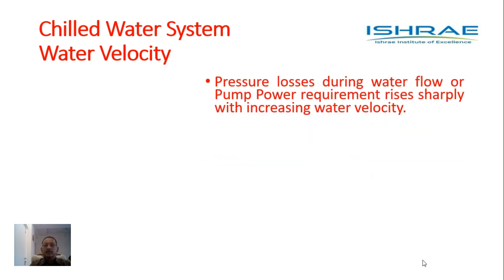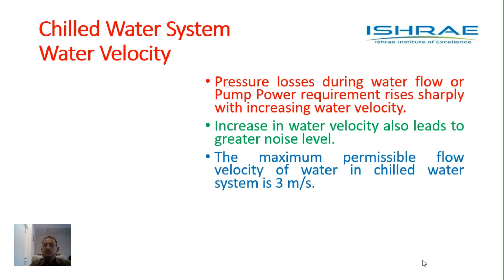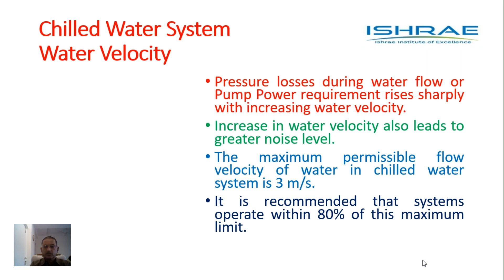Pressure losses during water flow, or pump power requirement, rises sharply with increasing velocity. The higher the velocity of water, the more will be the pump losses — that is, pressure losses — and more will be noise. Increase in water velocity also leads to greater noise levels. The maximum permissible flow velocity, because of these reasons, in a chilled water system is 3 meters per second. It is also recommended that systems operate within 80% of this maximum limit, so normally the velocity of chilled water through pipes is kept around 2.4 meters per second or below.